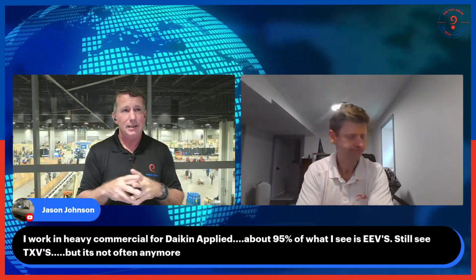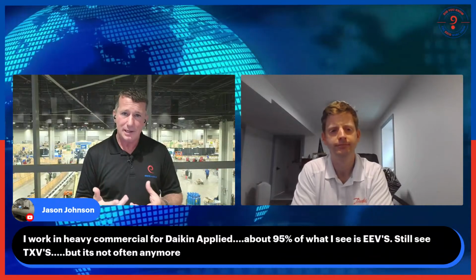Jason, you bring up such a good point. This is why we want to have this conversation. We've seen that transition, especially in the residential and light commercial, from fixed orifice, like piston style metering devices, and then we moved into thermostatic expansion valves. A lot of the industry sees electronic expansion valves as a small piece of the industry, but that is not so. We're moving into electronic expansion devices in a very fast way. And so we want everyone to have a better understanding of how they operate, how they're different, and how we can do diagnostics on each of those.